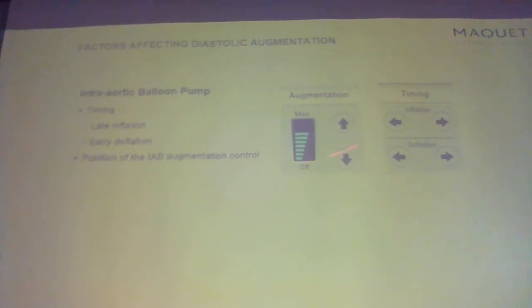There's going to be this little augmentation screen on here. It should always be at max. What that indicates is how much helium is being filled into the balloon. So we're going to maximize the balloon volume, so it should always be dialed up to max. You'll see this little green bar on the screen, and it should always be dialed up to max. The only time I can recall where we turned it down is one of the interventional cardiologists, that was how he liked to wean the balloon pump off. He would just dial down the augmentation, which, whatever.